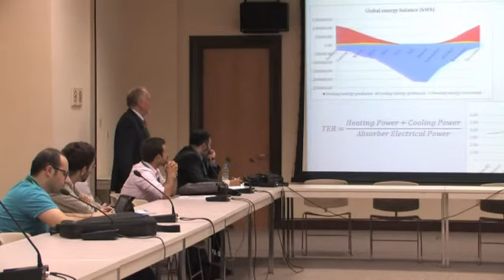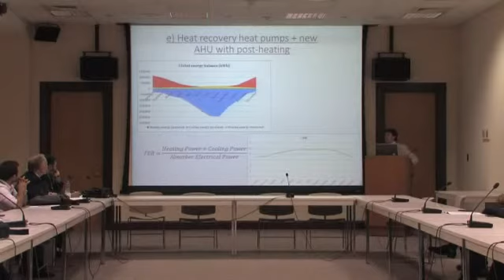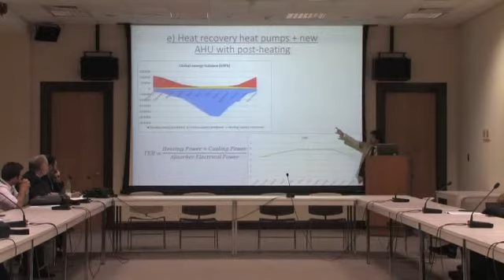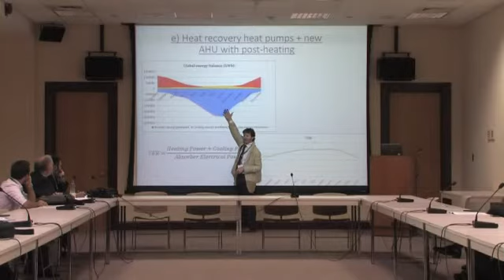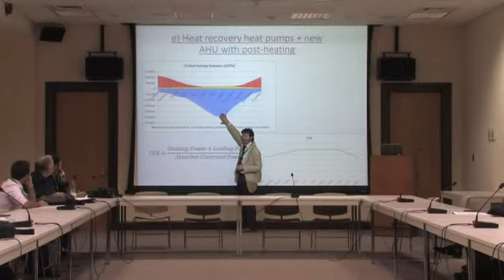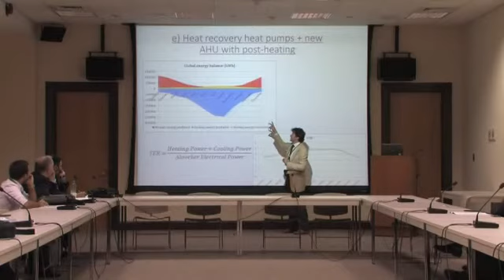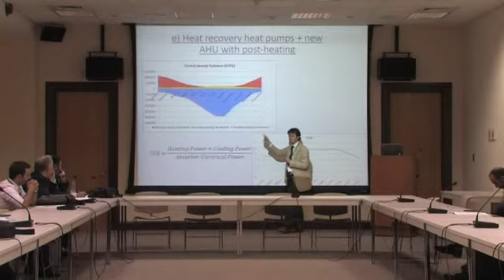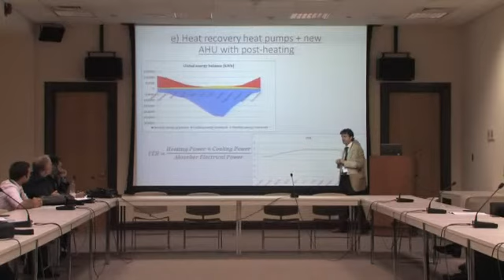This one, yes, without and with. Well, good question, it's not really the same. They are very similar, quite the same. There is a small increase if you are doing without. With, because you are recovering the heat, which is for the cost, not that much, not that high. I mean the big amount of that energy is anyway there. So if you compare demand for the post heating compared to the cooling load, it's much higher than the cooling load. But that's because you are considering only almost the net energy of the heating. Of course, if you are using boilers and you have partial load of boilers, then the efficiency of the boilers will decrease strongly, so you have double the consumption.